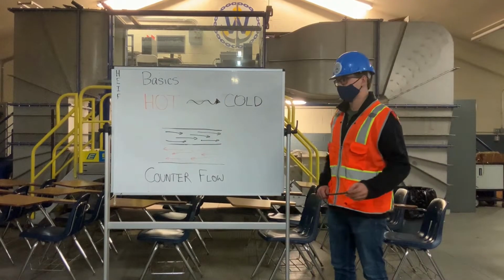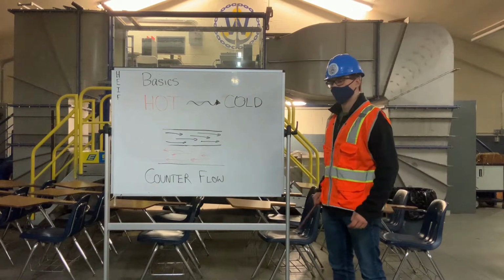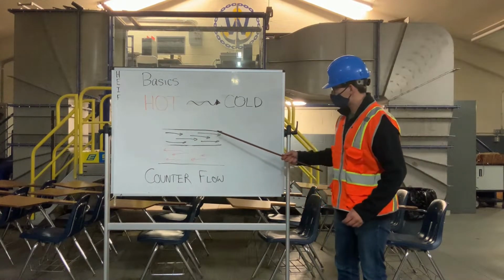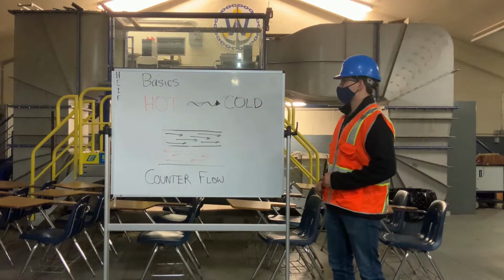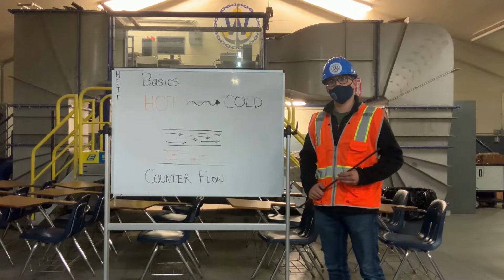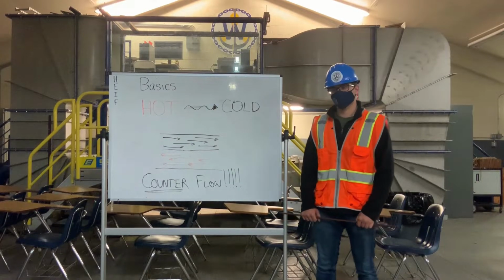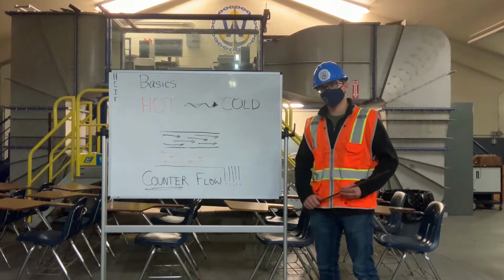To maximize the temperature differential, a method called counterflow can be utilized. In counterflow, the fluids are flowing in the opposite direction. This allows for the final temperature of the hot fluid to approach the initial temperature of the cold fluid. It is for this reason why counterflow is used in applications of heat exchangers.